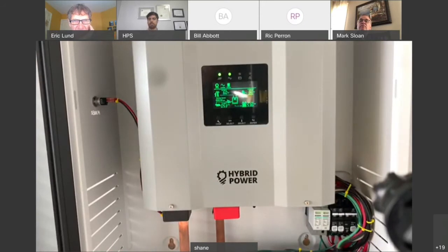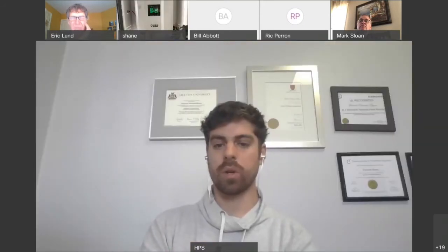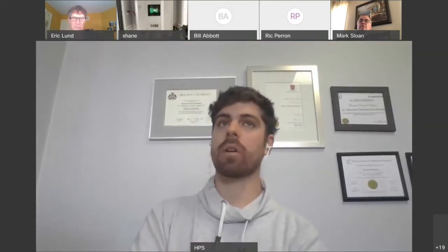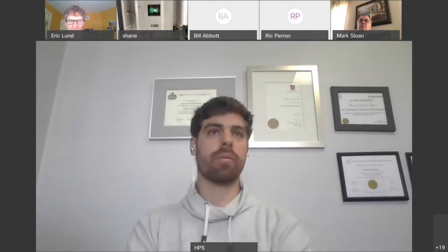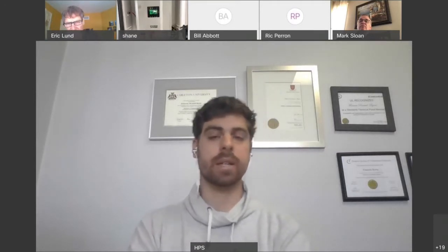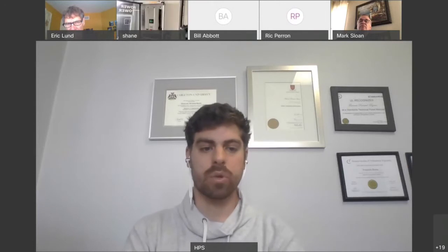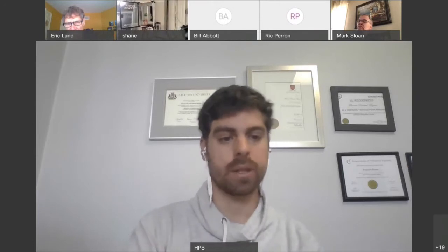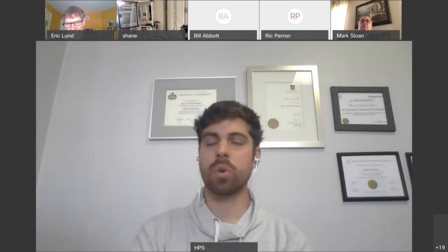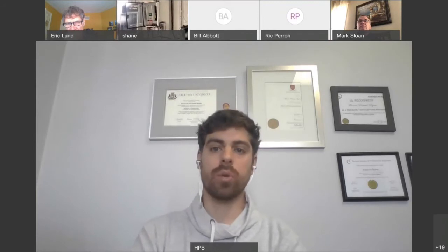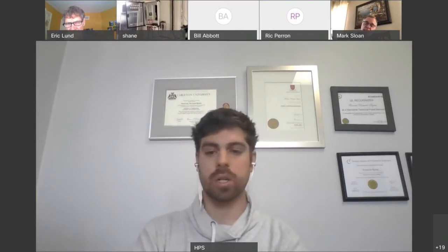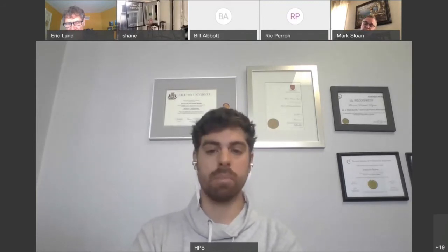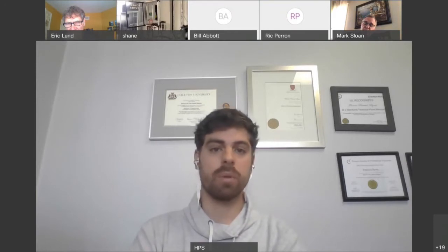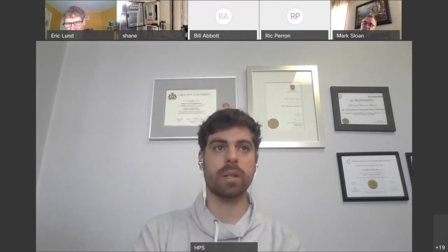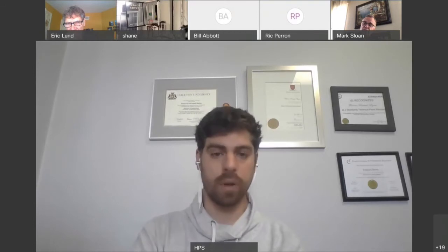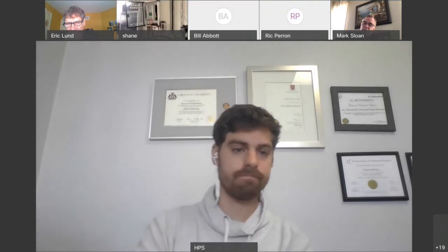And that's a really good point to mention. When you're comparing this to a generator, where you might get anywhere from a couple of seconds to 60 seconds of transfer time, it's important to note that with a system like this, the transfer time is about 20 milliseconds. So your computer's not going to shut off. You won't even see a blip. Quite frankly, most people who have a power outage with this system don't realize it until they hear their neighbor's generator kick in.